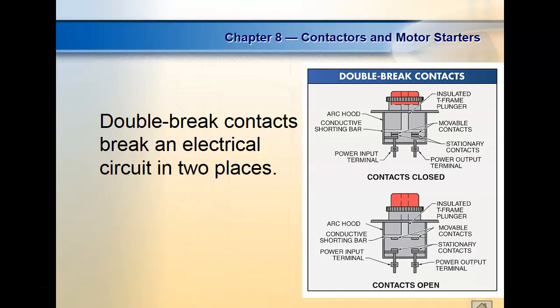So double break, what happens is this thing's spring loaded, it floats. So if one of them tries to get welded together, then it would tilt up and it would have a tendency to break contact. So you've got two chances of breaking a circuit, right? Okay. So you'll see a lot of double contact, double break circuits used.